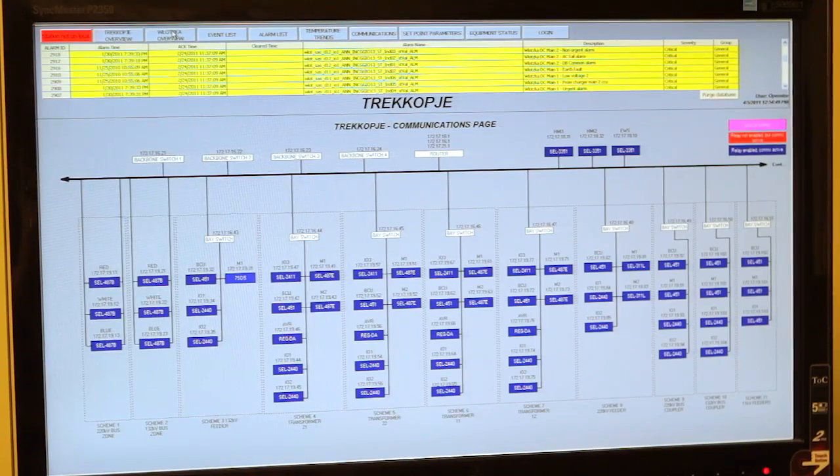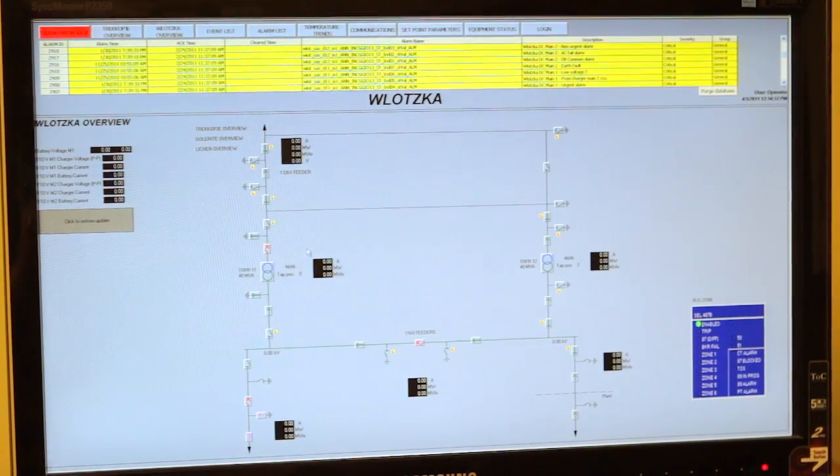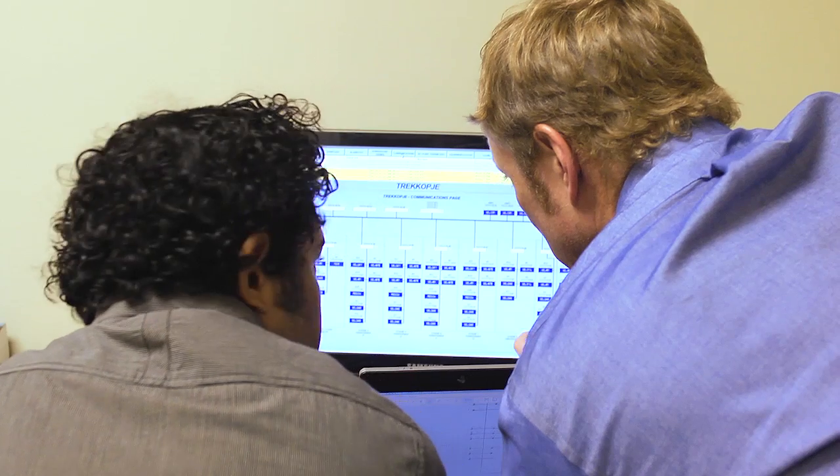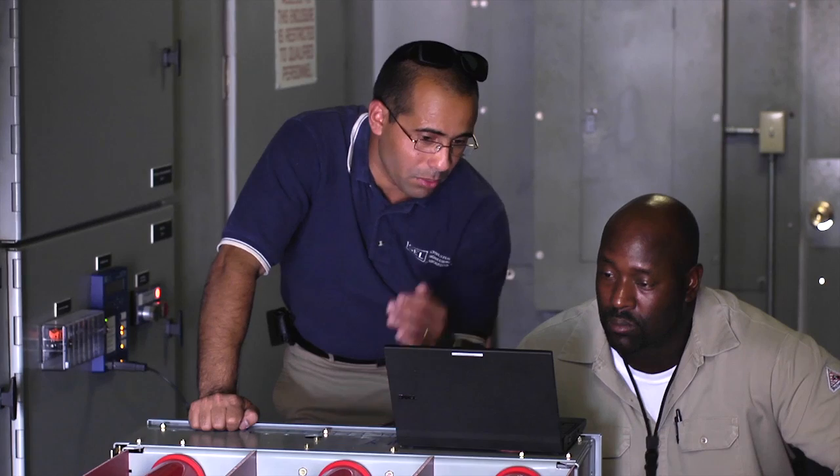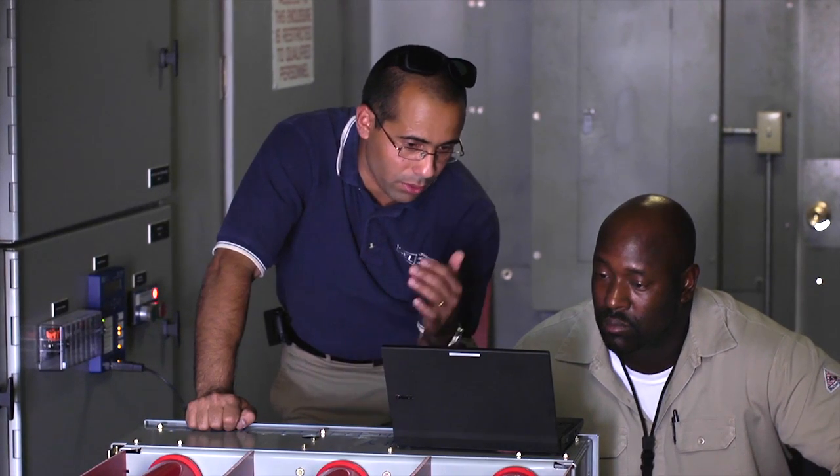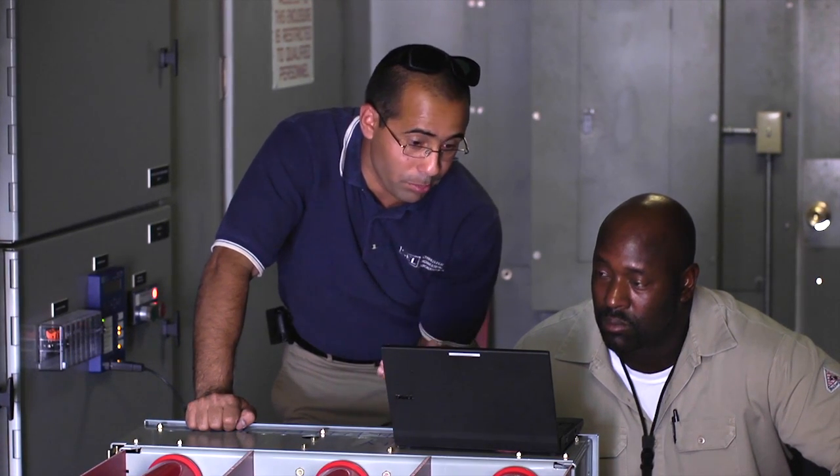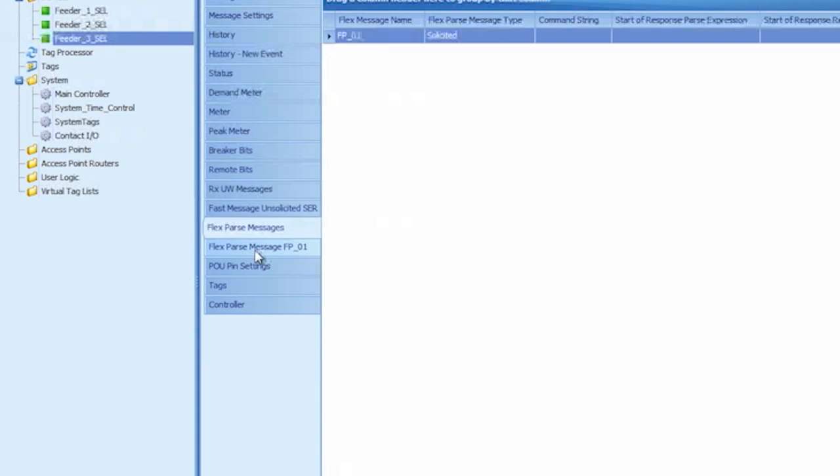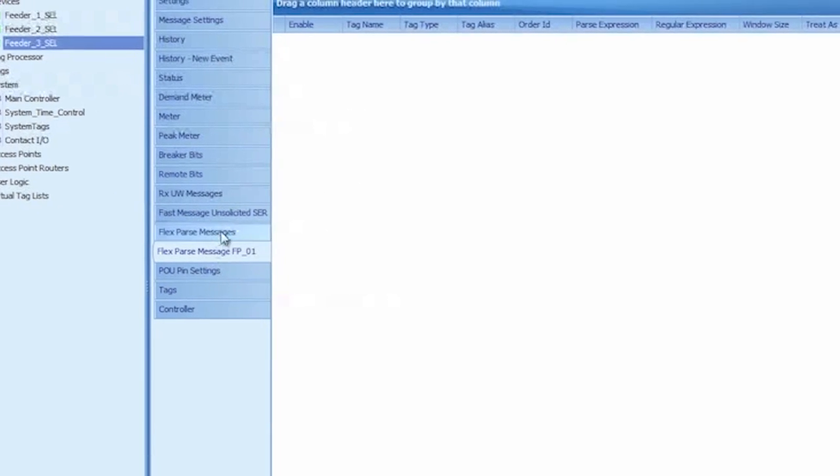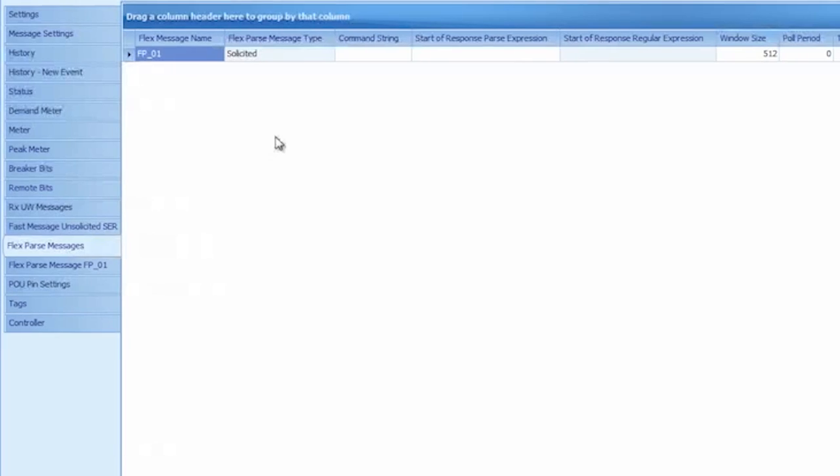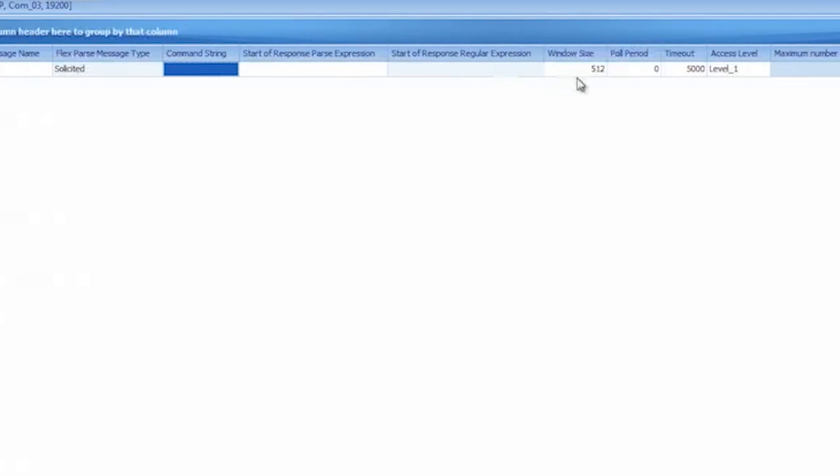When we developed the RTAC, we were very sensitive to make sure that it would be compatible with existing devices because we want to make sure that people maximize their investment in the devices that they already have. Some of the old devices were really designed to be communicated with by a human through hyperterminal or terminal emulation program. So we've designed into the RTAC the ability to communicate to those relays in that same manner. And then using a flexible parse program, we can parse out the information just as a human would and then store that information into tags.